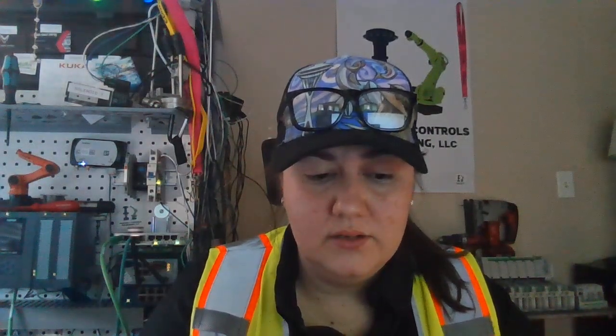There's a physical aspect in the beginning where we're actually checking wiring, right? With all the power off, we'll check all the motors and that they're all wired for whatever voltage we think they're supposed to be wired for. So if it's all 480, then it's all 480. If it's all 230, it's all 230. That's the normal three-phase in America, 230 or 480. So usually it's all one or all the other. There can be mixes, of course, but that's a typical setup. You're going to do IO checkout, and now you're going to check that all the motors are all 480 or all 230.